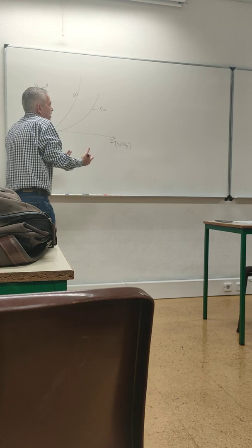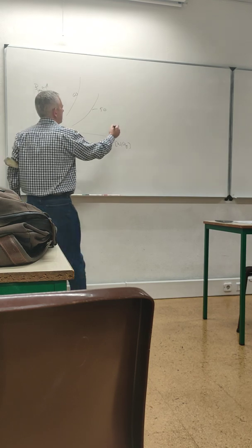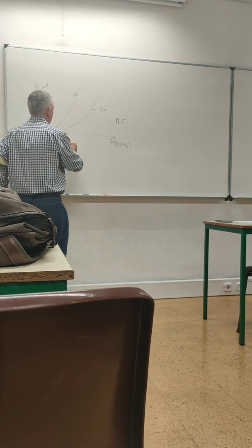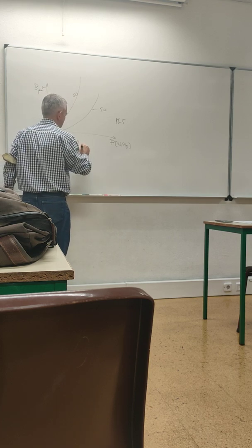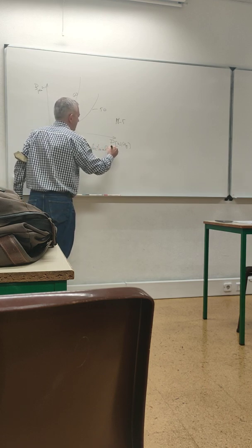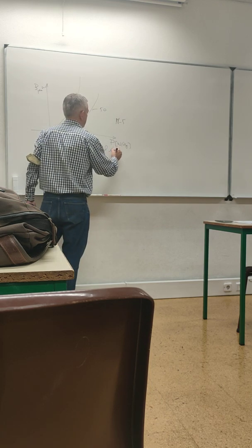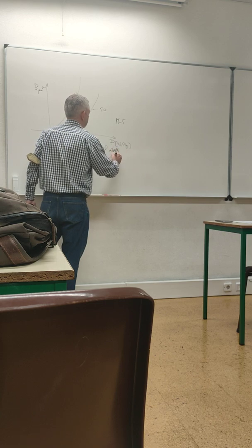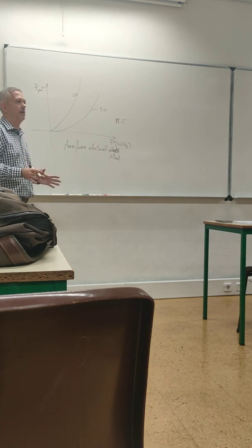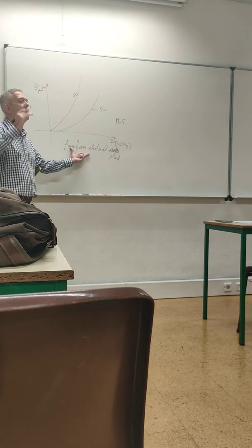And we have been working with two materials. One from the laboratory, the other one was M5 and so on. But we have a material that is called amorphous electrical steel. This has been used from many years ago. This material has been used in transformers with high power, because the power loss of these materials is very low.